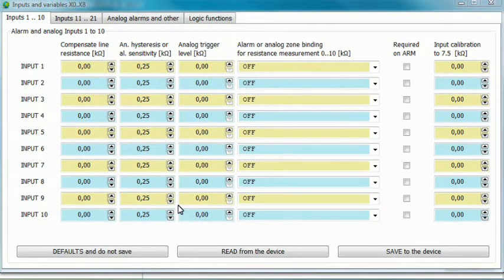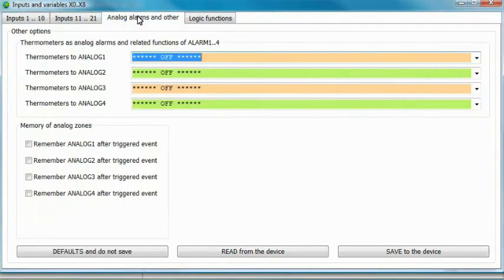Switch to the Analog Alarms and Other tab. The main difference between the normal alarm zones and the analog alarm zones is that the analog zones do not remember an alarm after its cause has disappeared. You can, however, activate the Remember Analog After Triggered Event option. The device will then remember that an analog alarm was triggered.